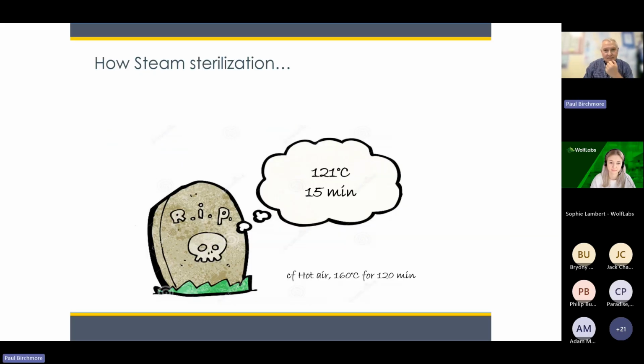Steam sterilization. Autoclaves use the heat of steam to kill bacteria in a contaminated load. The principles of sterilization have not changed in the past 150 years. The monitoring systems and the ways of checking effectiveness have evolved, but the principles are very similar to a pressure cooker in that sense. So why steam?